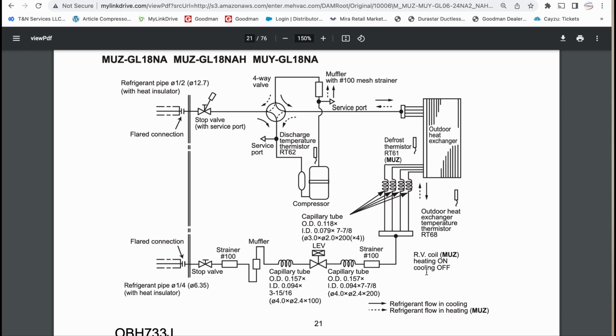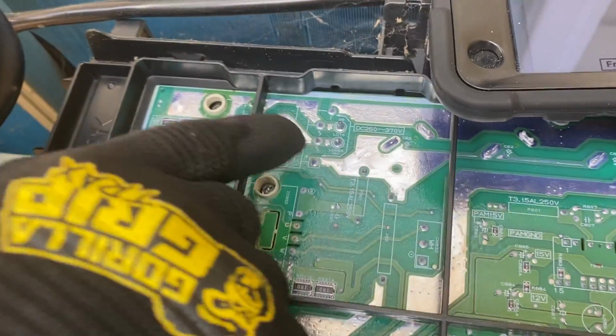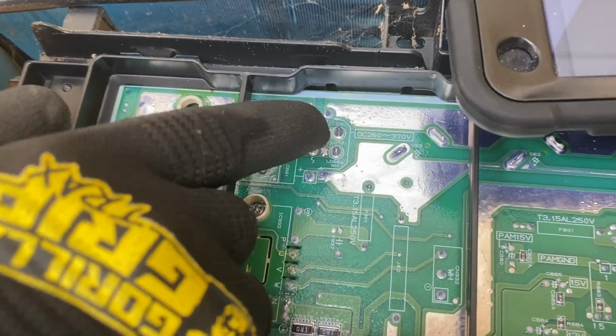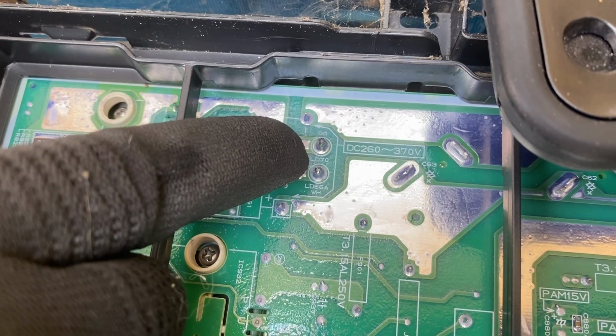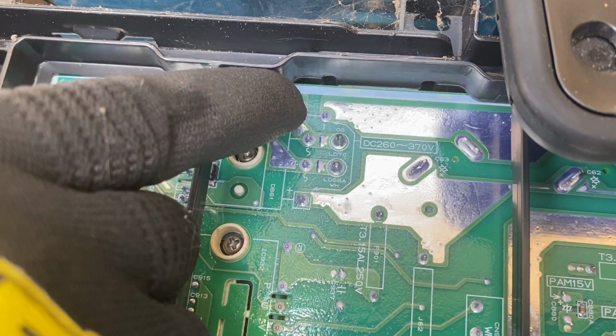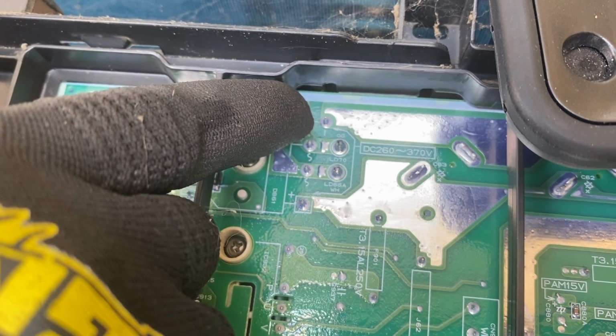Like I said, we do have a couple units that actually energize in cooling, so you need to come to the manual if you're having a reversing valve problem and find out, are we energizing heating or cooling? And then check it. Which is right here. So those same points on that test point diagram are right here.